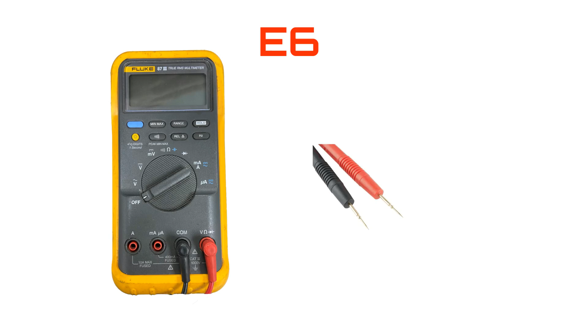If your unit is displaying an E6 error code on the ODU display, the voltage signal that PFC sends to the main control board may be abnormal and the AC unit will turn off. To troubleshoot this error code, you will need your multimeter with needle point test leads.